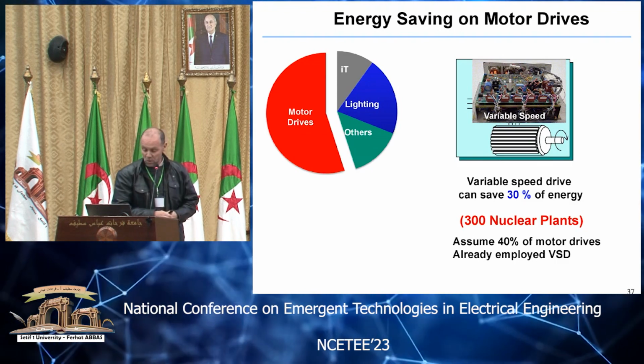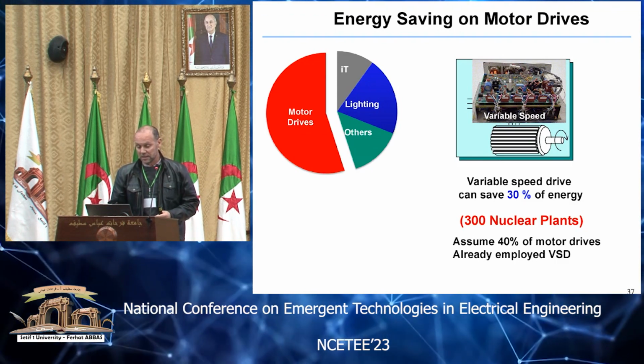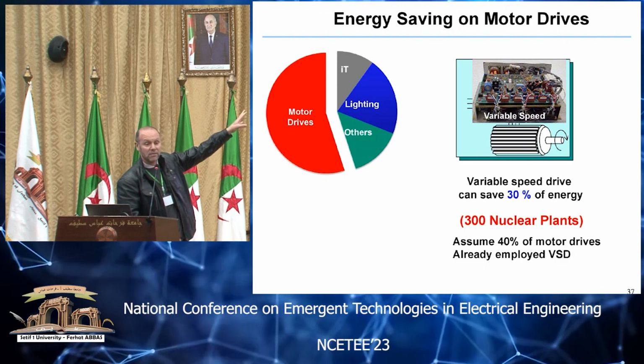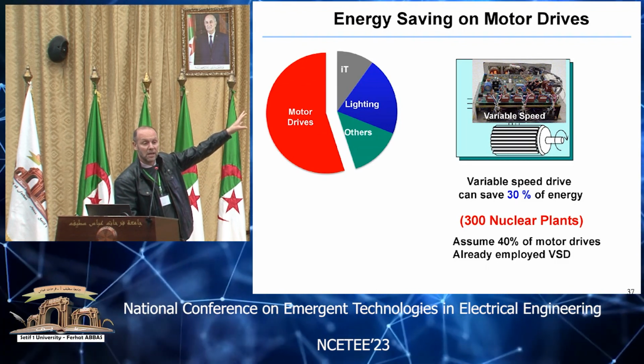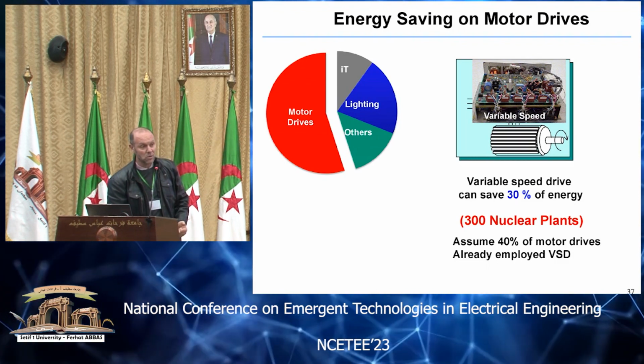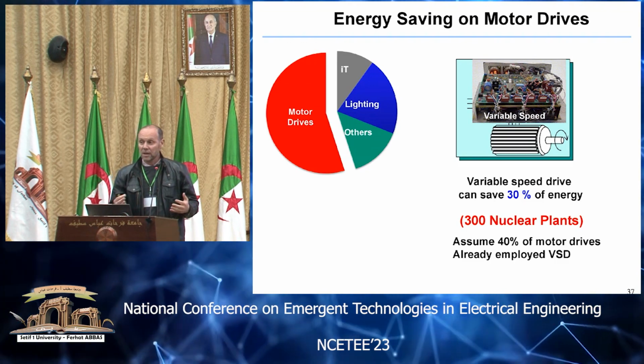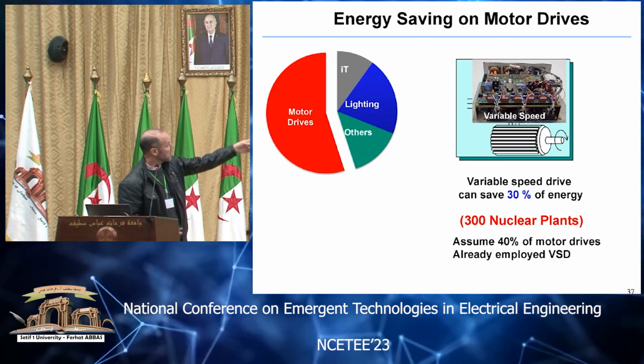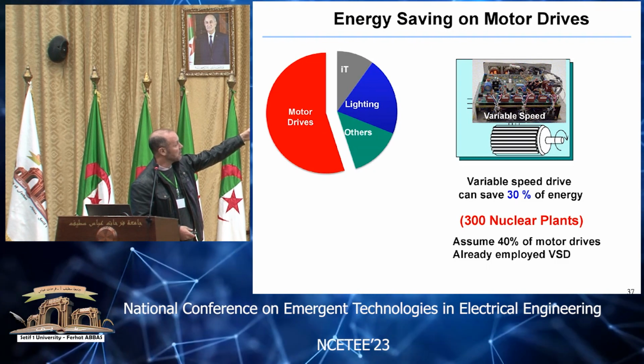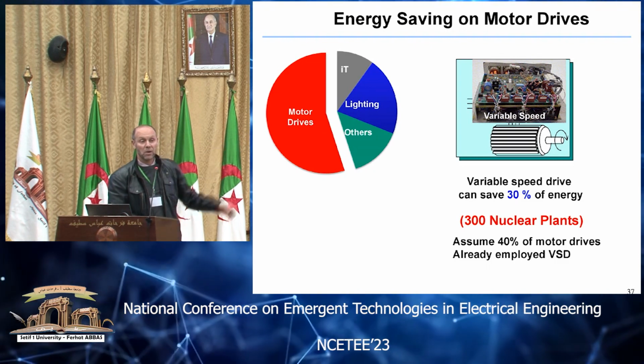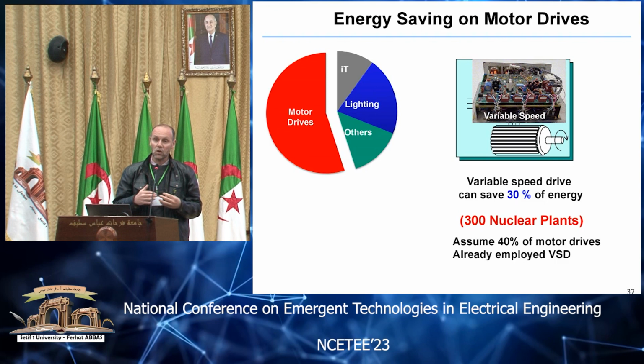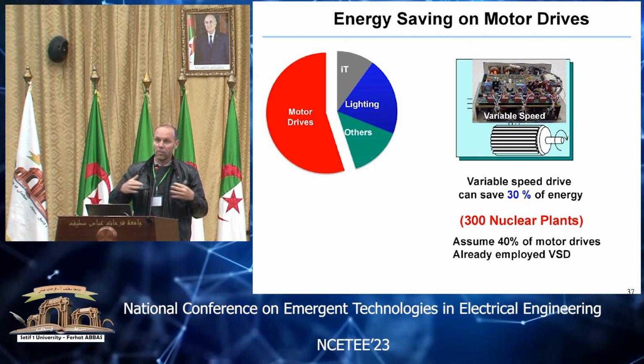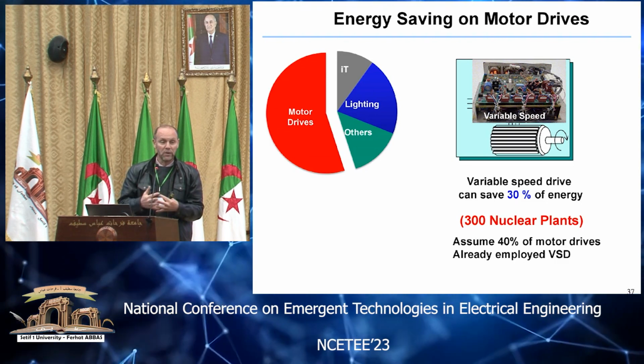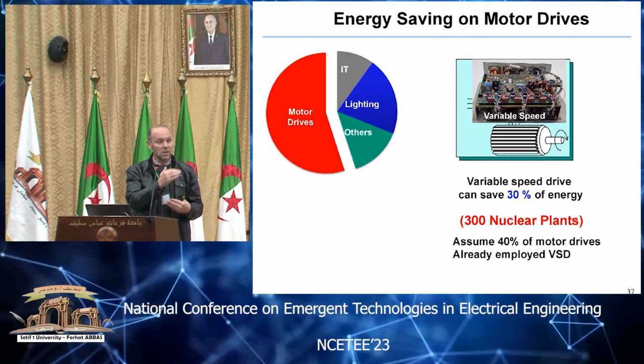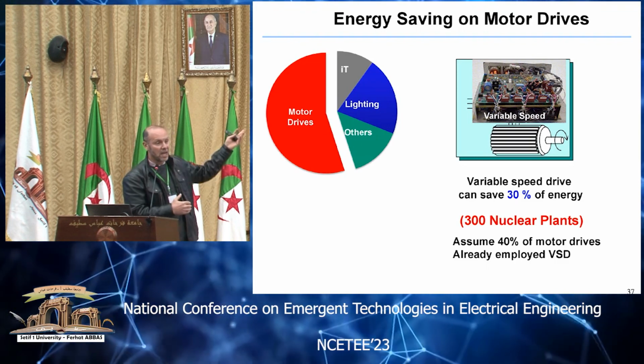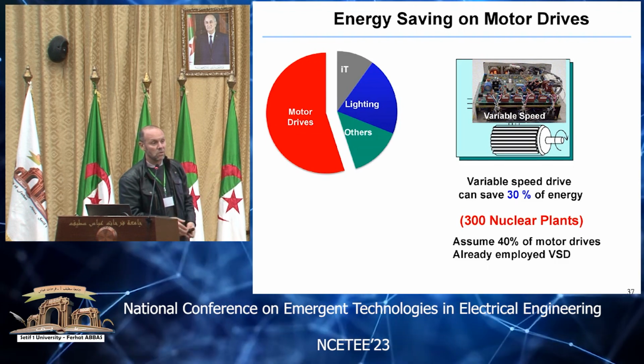So if we use VSDs and VFDs, variable speed drives, which are used to reduce energy consumption in electric motors, we can save around 30%. I'm talking about motors that don't operate at full load, because if a motor operates at full load, we don't need the VSD or VFD. But if the load is changing, VFDs and VSDs become important for energy saving.